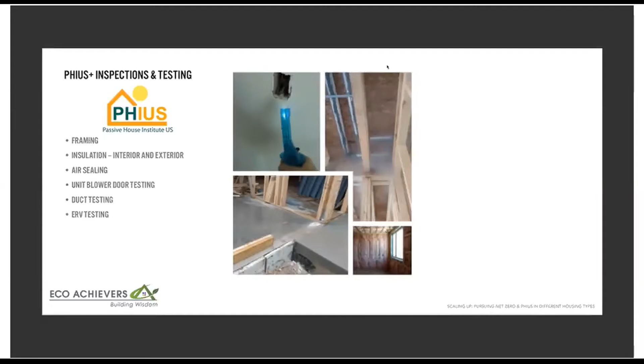The reason why the ERV duct testing is important is because there are performance thresholds in a different vein, but still performance thresholds for your ventilation. If you don't pay attention to that ductwork, you're going to have leakage and it will not get to its intended target, which will interfere with your certification.